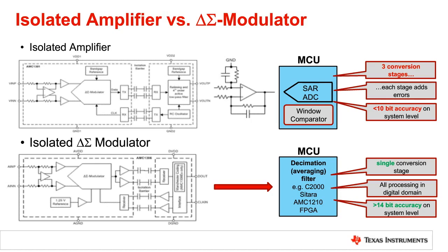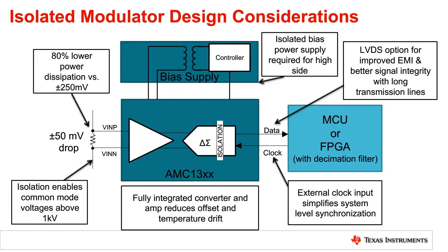Looking a little closer, we're going to use one of the AMC 13XX family of devices. This particular one has a 50 millivolt drop across the input. So essentially what we'll do is tie that back to what we talked about earlier with shunt sizing. When we looked at VS range divided by gain, we can just use the output of that system and use a 50 millivolt range.